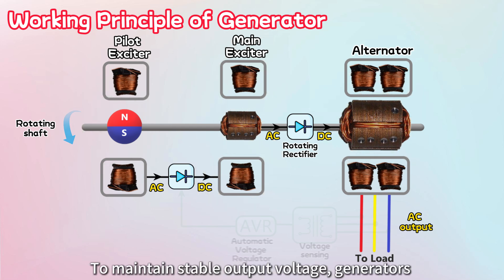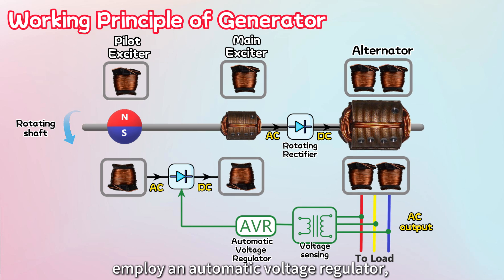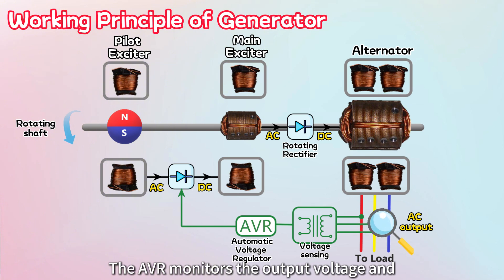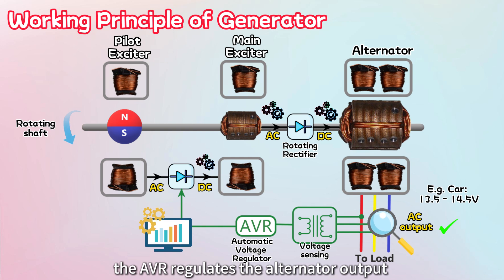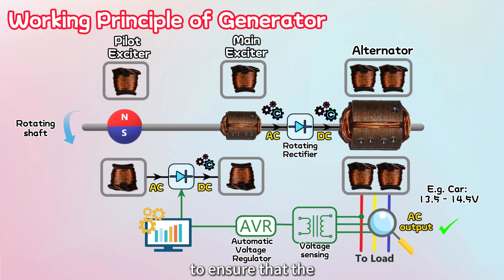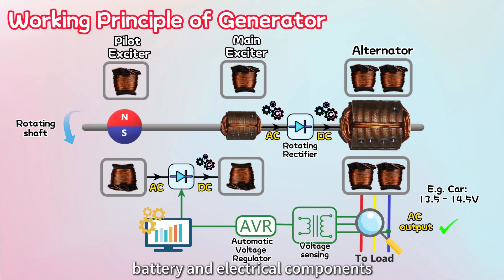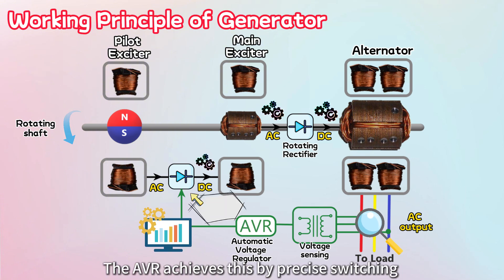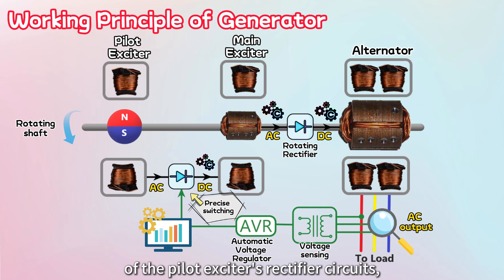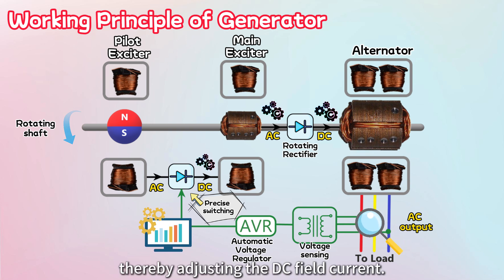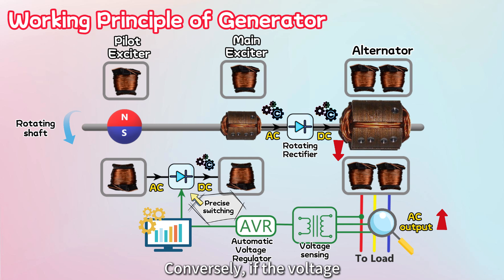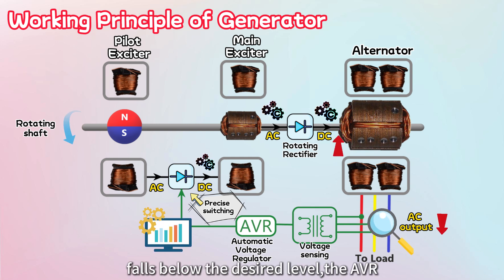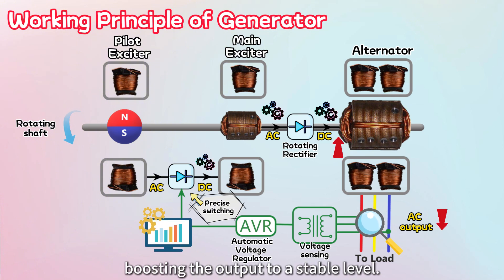To maintain stable output voltage, generators employ an automatic voltage regulator, or AVR. The AVR monitors the output voltage and adjusts the DC field current in the rotor to ensure the voltage stays within a specific range. For example, in cars, the AVR regulates the alternator output between 13.5 and 14.5 volts to ensure the battery and electrical components function properly without damage. The AVR achieves this by precise switching of the pilot exciter's rectifier circuits, thereby adjusting the DC field current. If the output voltage is too high, it decreases the DC field current to reduce the voltage. Conversely, if the voltage falls below the desired level, the AVR increases the DC field current, boosting the output to a stable level.